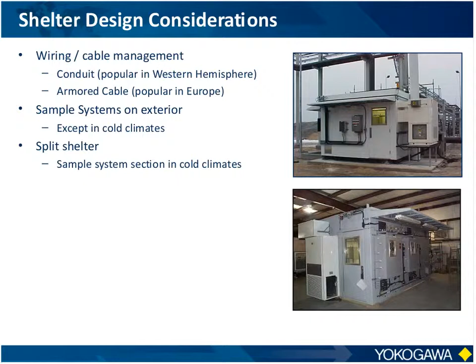Now, obviously in some climates, like Russia or Canada, you may still have to put the sample systems inside just due to the sheer cold during the winter. In those situations, some customers will run a wall down the center of the inside of the shelter to split it, so one side has the sample systems to help segregate in case of a leak, and the other side is where the technician would normally work on the analyzers.